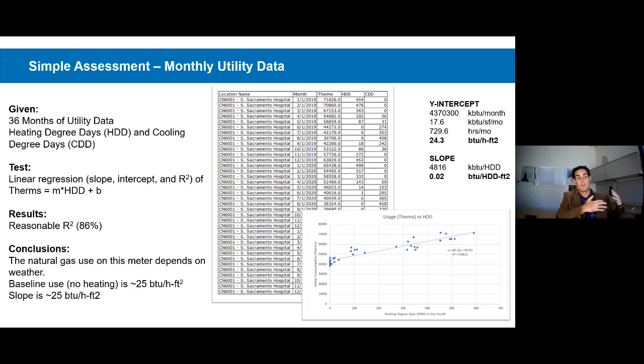So the y-intercept of that line tells us how much reheat is being used in the non-heating months or in the summertime. You can actually divide that number by 730 hours a month and the building size. And in this case, you'll see there's an average of 24 BTU per hour per square foot every hour of reheat or baseline heating energy. It's a pretty big number. And then the slope of the line tells us how strongly this building responds to cold weather, the strength of that correlation. And in this case, every heating degree day in the month adds 0.02 BTU per square foot.